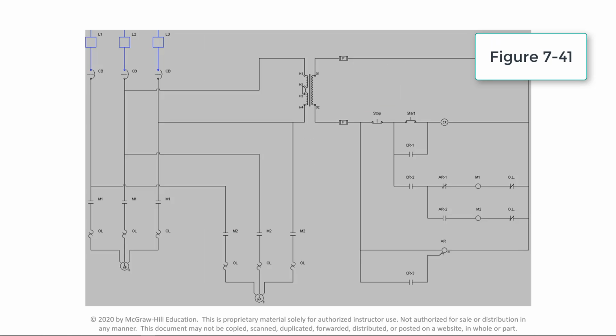This video demonstrates the operation of an alternating relay circuit used with a duplex pumping system. In this application, two identical pumps are used for the same job. A standby unit is made available in case the first pump fails. However, a completely idle pump might deteriorate and provide no safety margin.